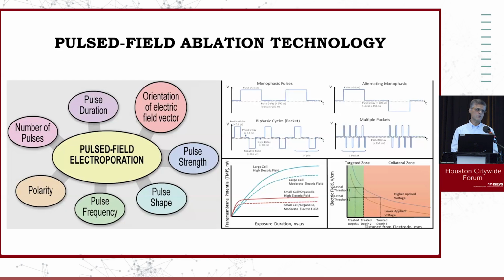One of the problems so far with pulse field ablation has been that it's not standardized, as opposed to radiofrequency ablation and cryoablation, which have been around for a long time. Catheters and the energy source are all fairly standardized. In pulse field ablation, we have different shapes and sizes of catheters. We have different protocols for how the energy is applied. We have different energy strengths being used in different generators. So there's no particular standard for PFA yet. I think that as time goes by and we understand this technology better, there will be a move towards a little bit more standardization.